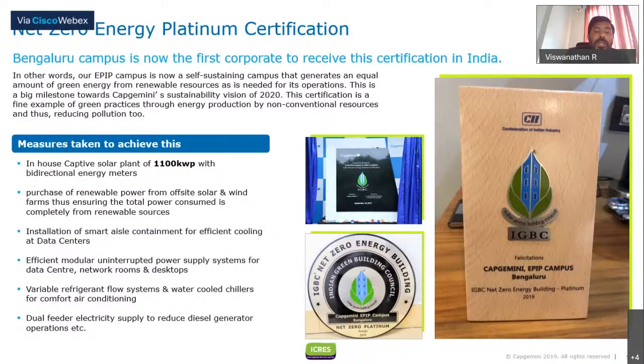So what we have done in the data center is a smart aisle containment, which means air conditioning is supplied only for the racks which require cooling, not the void space. The void space within the data center we do not cool, which I will show in the subsequent slide. And for the air conditioning system, we have installed a variable refrigerant flow system, which is an energy efficient system. And we have also installed water cooled chillers for comfort air conditioning.